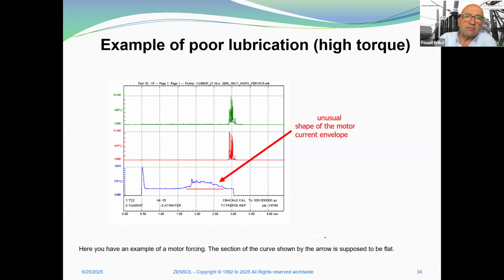Here we can see an example of poor lubrication. It's an unusual shape of the motor current envelope. In fact, here it has to be flat, and if it's not, this means that the current is forcing.